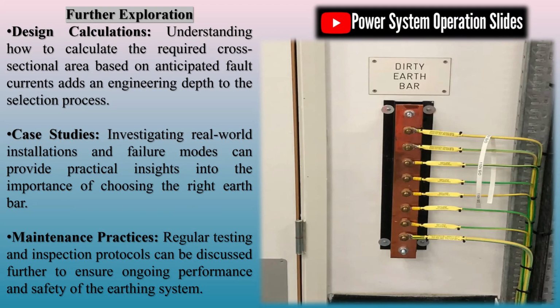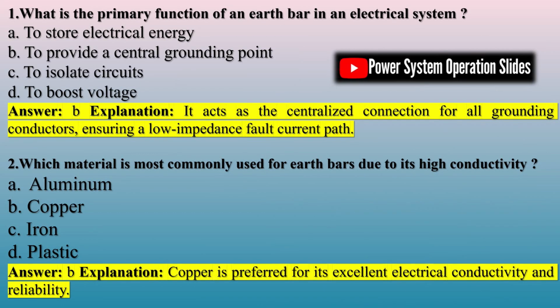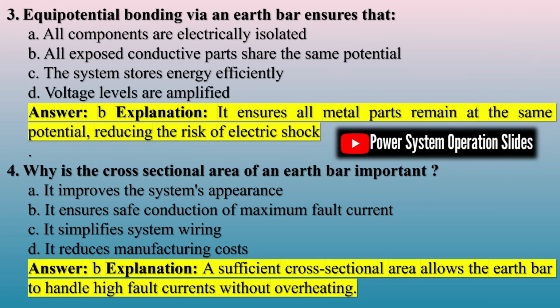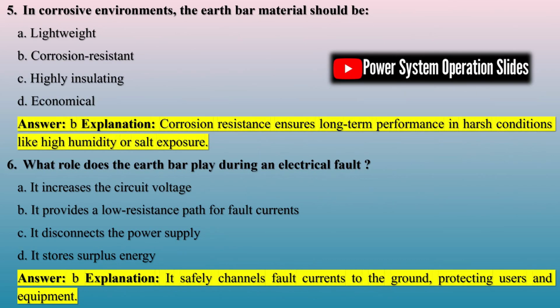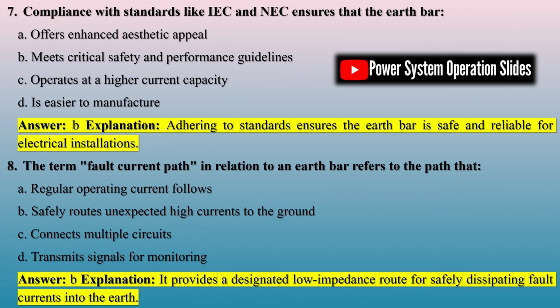An earth bar is a metallic conductor that serves as a central connection point for all conductive components and services. These may include water and gas pipes, electrical power systems, telecommunications infrastructure, and data cables. Standard earth bars offer a practical and efficient means of establishing a common earthing point. Their design varies depending on the specific application they serve. For example, telecoms earth bars, illustrated on the right in the figure, are distinct from industrial or power earth bars, each tailored to meet the demands of their respective environments.